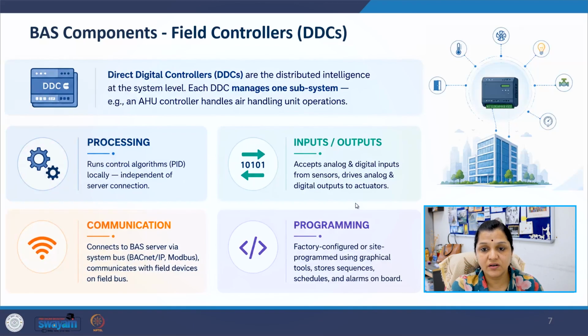Controllers receive analog and digital inputs from sensors and send output to actuators. Communication occurs through both field buses and system buses. Protocols such as BACnet IP and Modbus are commonly used for controller communication. DDCs also store schedules, set points, and alarm thresholds. Some controllers are factory configured, while others are programmed on site using graphical tools. Distributed control improves reliability because local systems continue operating even if high level systems experience interruptions.